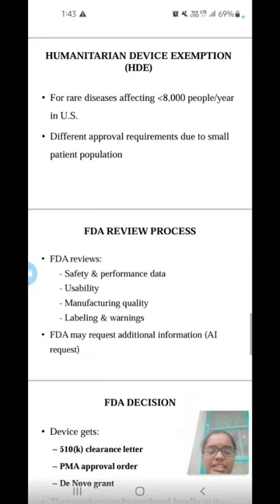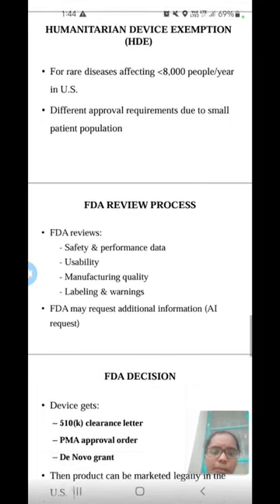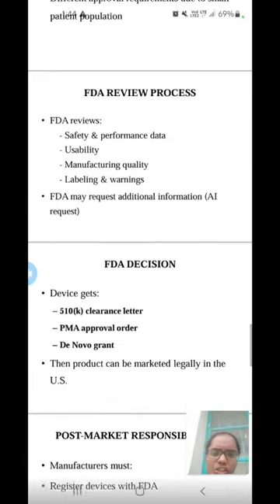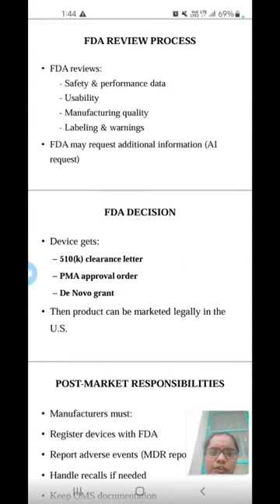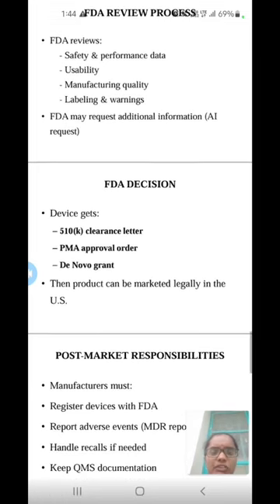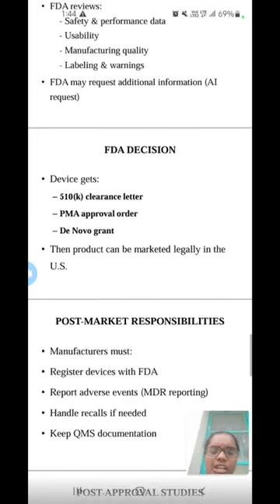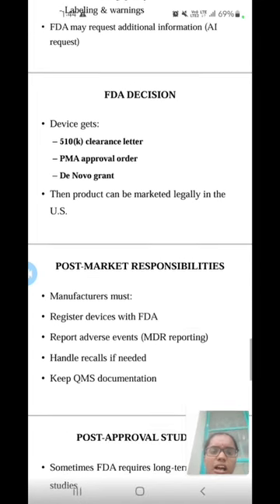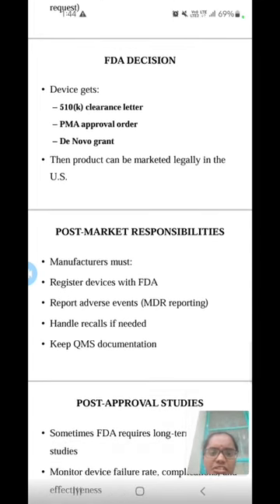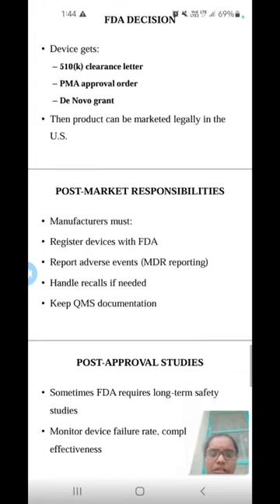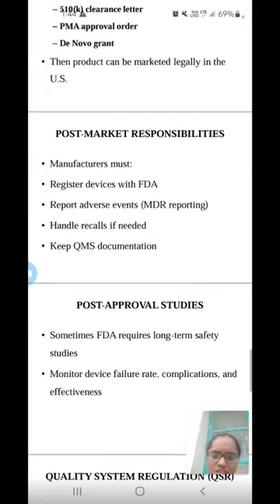Next, HDE is for rare diseases affecting fewer than 8,000 people per year in the US. There are different approval requirements due to the small patient population. FDA review process: it reviews safety and performance data, usability, manufacturing quality, and labeling and warnings. FDA may request additional information. FDA decision: a 510K clearance letter, PMA approval order, or de novo grant. Then the product can be marketed legally in the US.